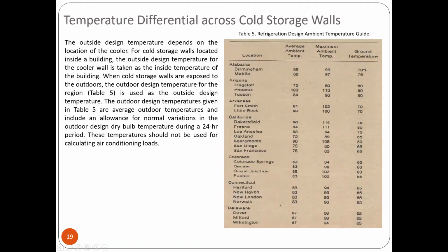The outside design temperature depends on the location of the cooler. For a cold storage wall located inside a building, the outside design temperature for the cooler wall is taken as the inside temperature of the building itself. When the cold storage walls are exposed to the outdoors, table 5 is used for the outside design temperature, for the region. This is for air conditioning, but we have no air conditioning yet. The outdoor design temperatures given in table 5 are average outdoor temperatures and include an allowance for normal variation in the outdoor design dry bulb during a 24-hour period. This temperature should not be used for calculating air conditioning load, since it is only for 24 hours.